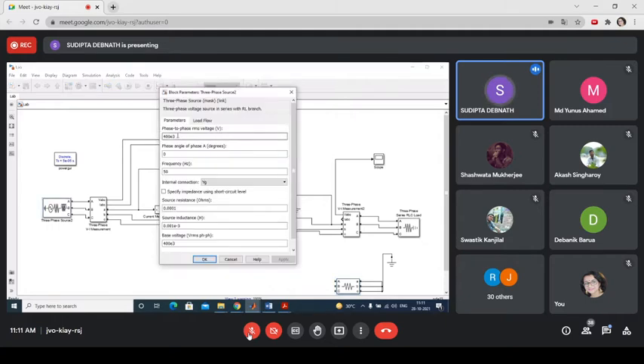See, the voltage is 400, E3 means 10 to the power 3, so 400 kV, phase to phase voltage. Phase to phase means from one phase to another phase, that means it is the line voltage, and it is the RMS value. So it is actually VL.